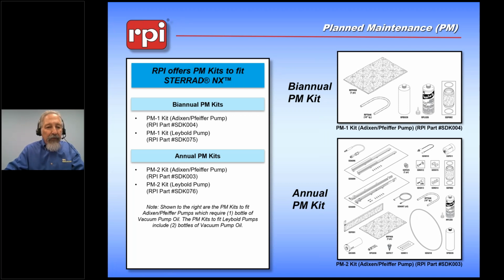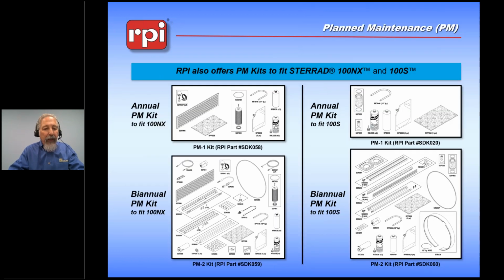This PM kit is for the NX, but we also have available kits for the 100 NX, including basically an oil change kit, as well as the full rails and oil change kit, including a door gasket. Within the oil change kits, we have coalescing filters to be sure that the pump doesn't spew oil into the catalytic converter or into the air. We also have both an annual and a biannual PM kit for the 100S.